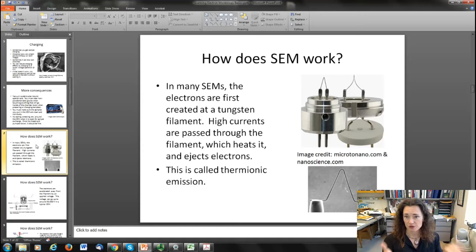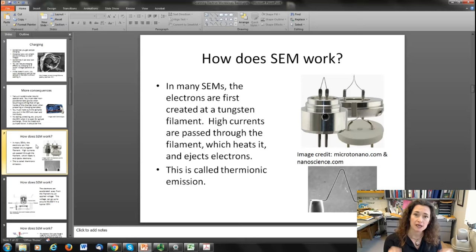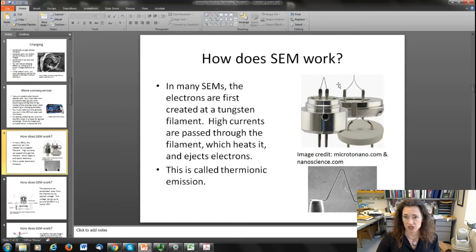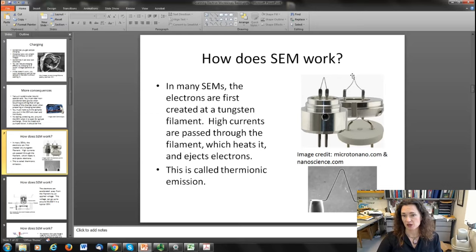Let's discuss how scanning electron microscopes work. The most common electron source is basically just a filament — you have a tungsten filament and you pass a current through it. In response, the filament heats up and that heat gives some of the valence electrons enough energy to be freed and kicked off. This is called thermionic emission. You can see typical SEM tungsten filaments bent into a V or sharp point, which helps collimate the beam. The electric field is highest at the sharpest points, and that's where the majority of electrons are emitted from.